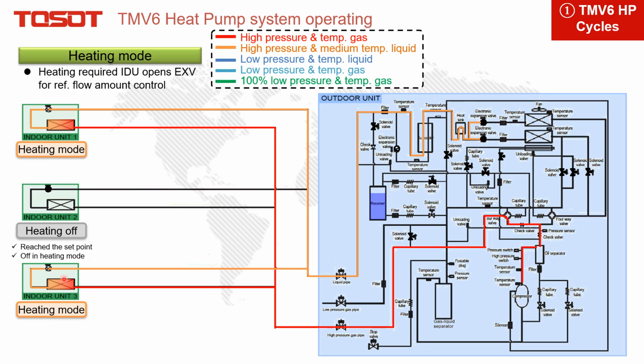Also note that these two EXVs of the indoor unit are not for metering. Their purpose is just to adjust the refrigerant flow to make a balance between the indoor units. And the metering is always done in the outdoor unit, this one. Then it becomes low pressure and temperature liquid, absorbs heat at the outdoor heat exchanger, flows back to the valve, then to the gas liquid separator, and lastly goes back to the compressor.